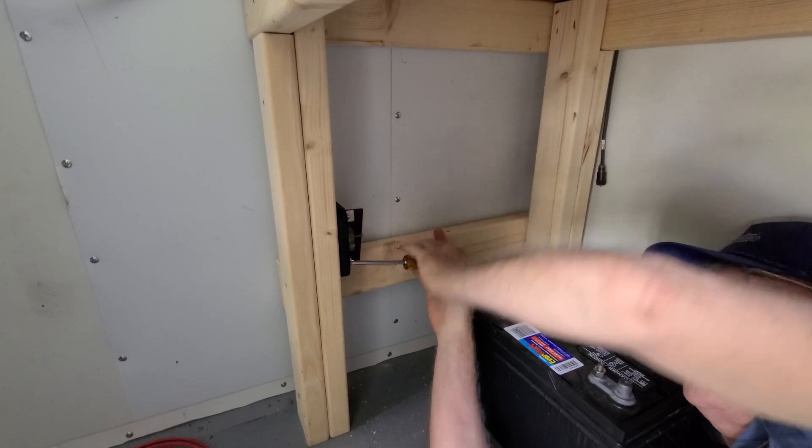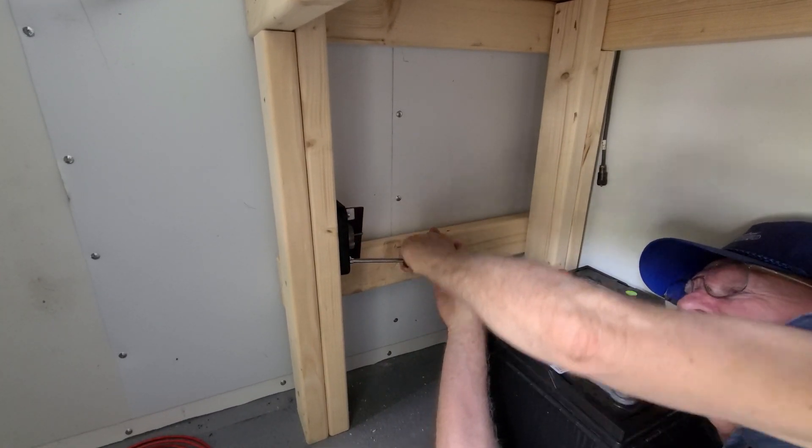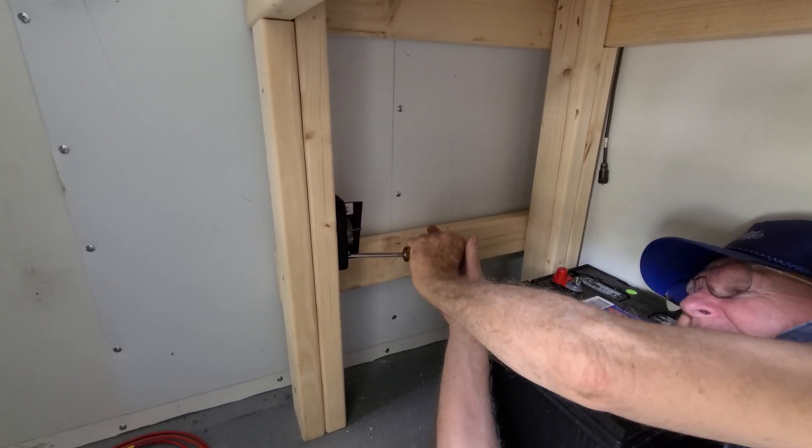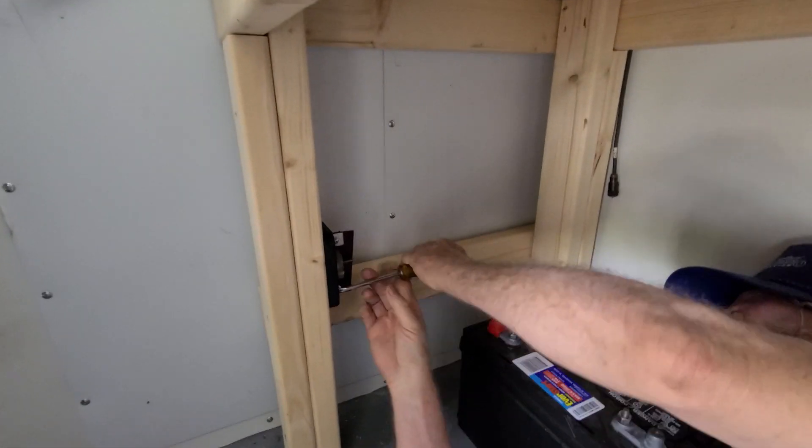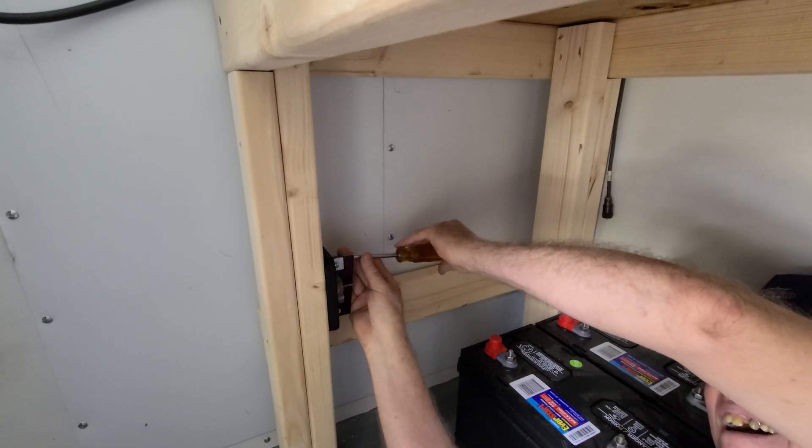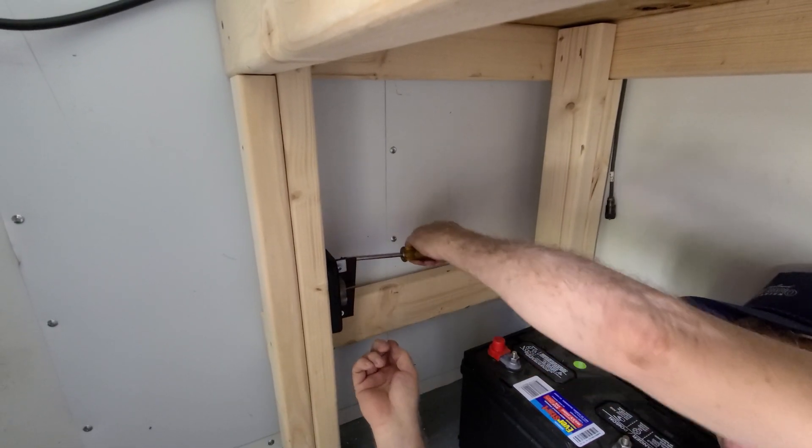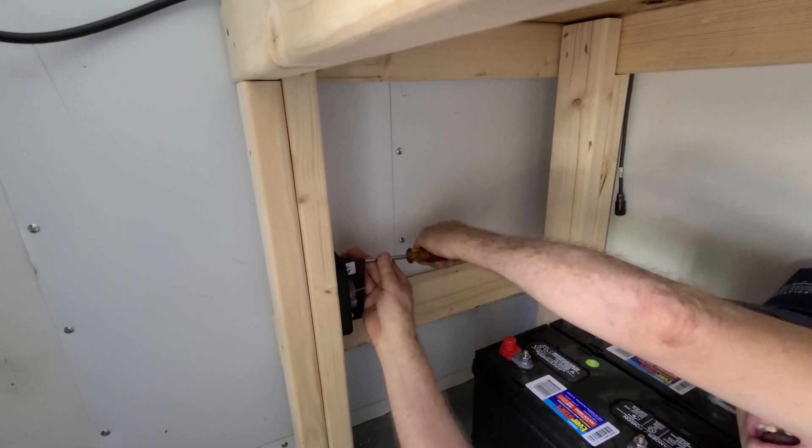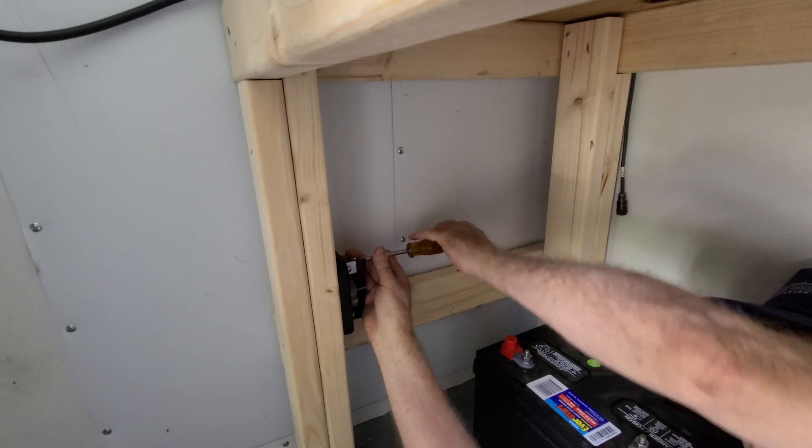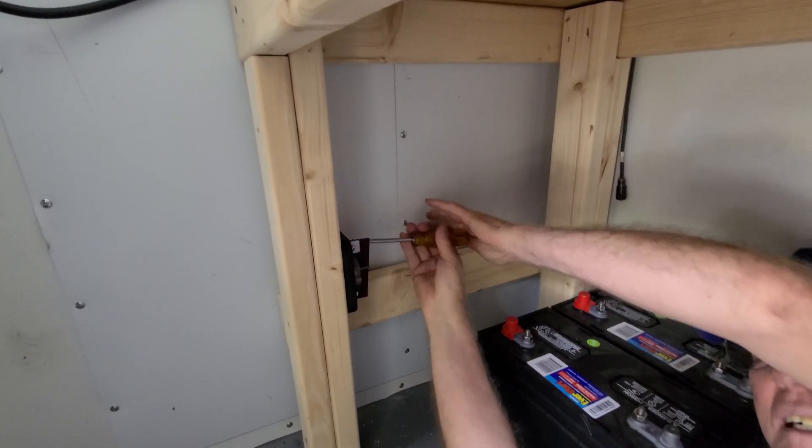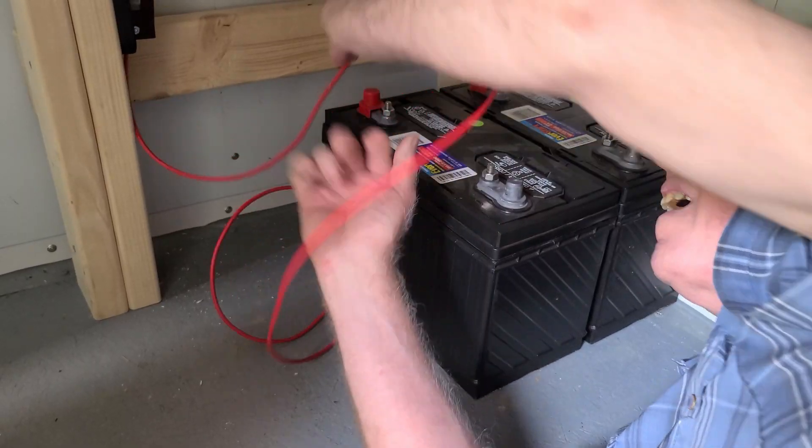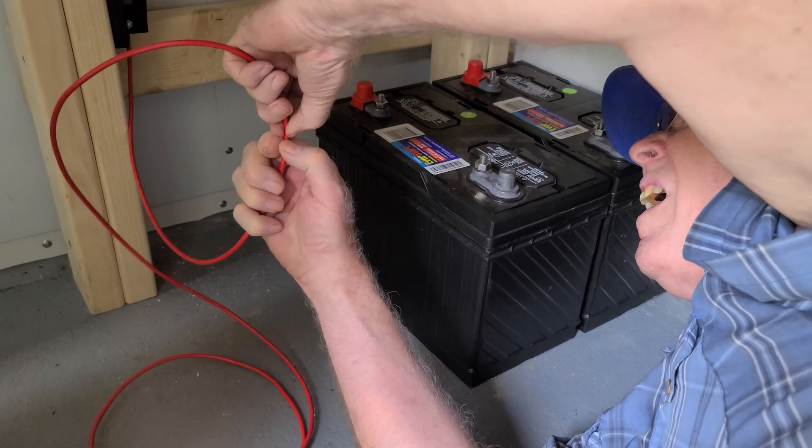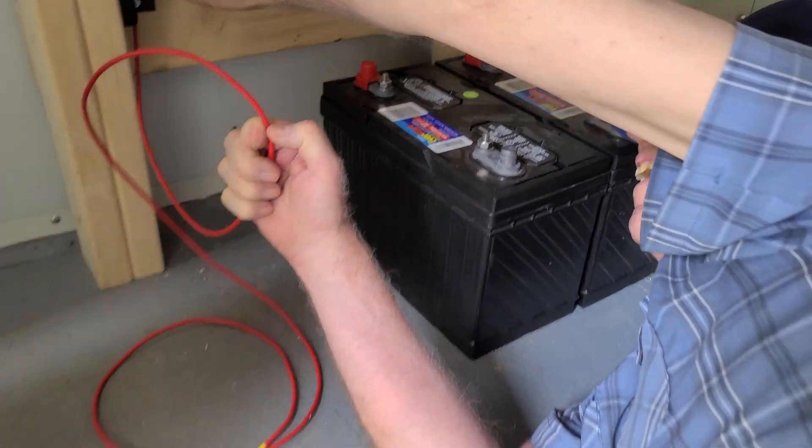We're just finishing up installing this distribution block. We're not using a BMS, so we have to make sure that all of our leads, positive and negative, are as equal in length as possible to achieve approximately equalization across all the batteries for both charging and discharge.